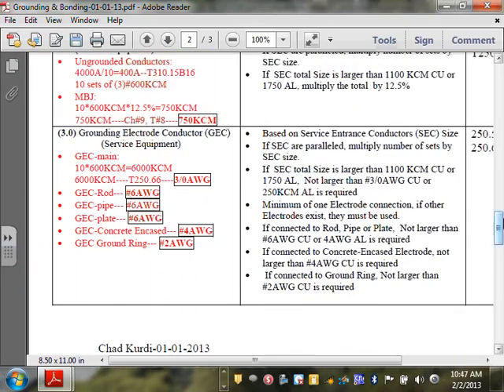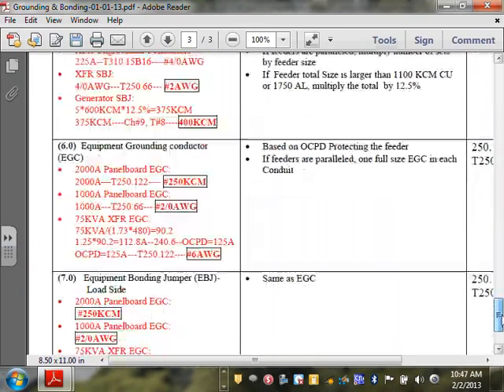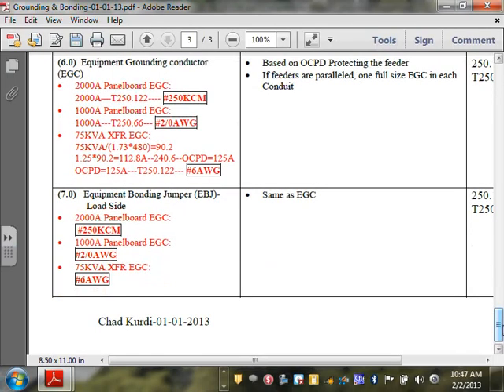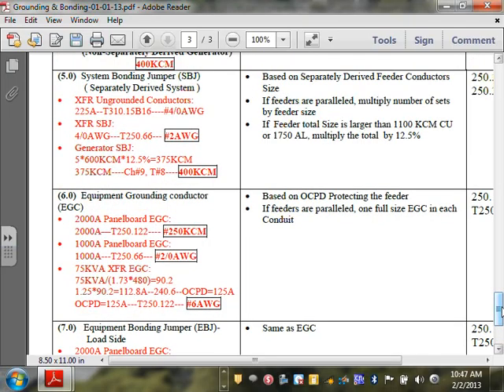I hope these numbers make sense for all of you, all the way to number 7. Number 6 is called an equipment grounding conductor. These are terminology from the code, EGC. It's based on the overcurrent protection device for the feeder. If feeders are paralleled, one full-size equipment ground conductor in each conduit. One full size. If you parallel, you don't cut them.